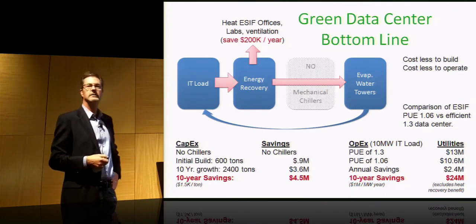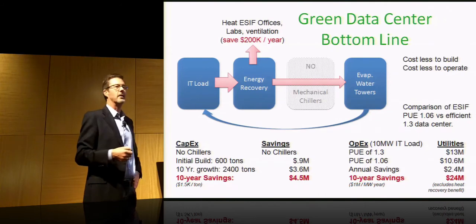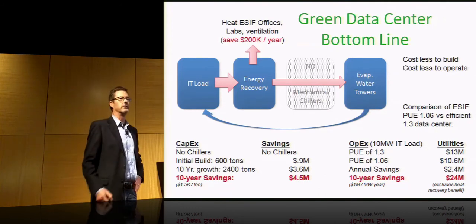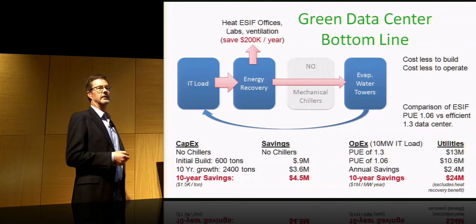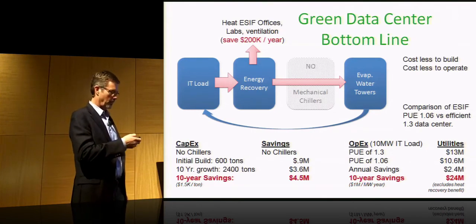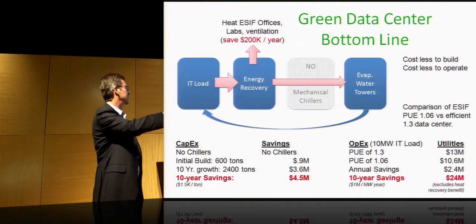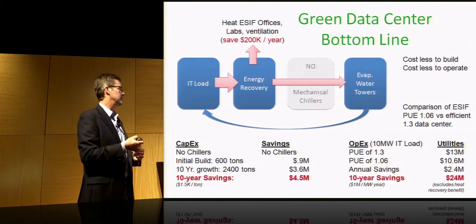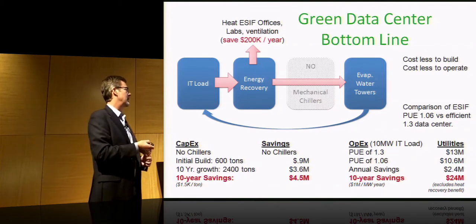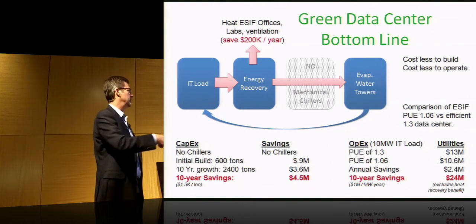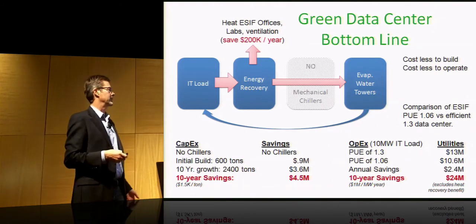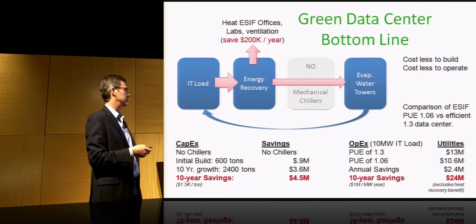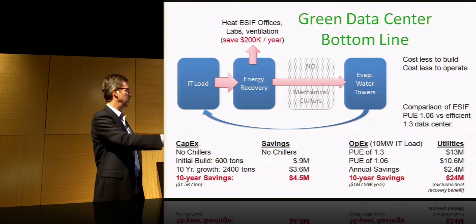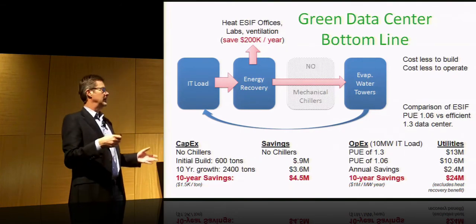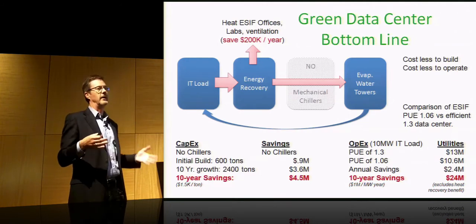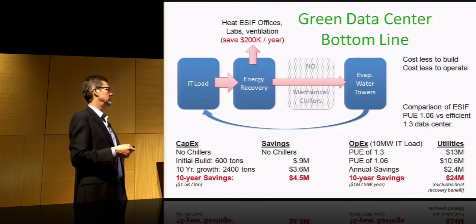In terms of ROI, what's the bottom line? We've done this because it makes sense to us, it's part of our mission, but the bottom line is it does cost less. On the CapEx side, we didn't build a building that required chillers, so we eliminate that cost. If we had required chillers, it would have cost us $4.5 million worth of equipment to install, plus the electrical infrastructure to support those. On the OpEx side, if we compare our PUE for a data center with a 10 megawatt load, that's the standard of how these comparisons are made, if you were going to do a full build out.